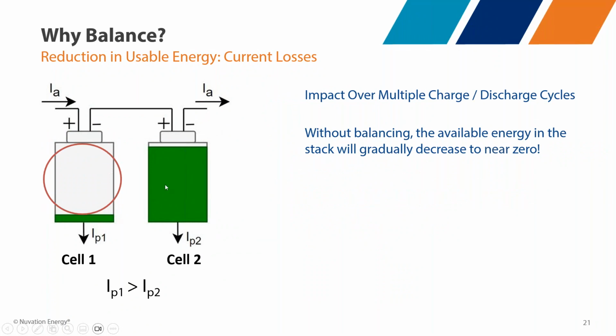If you go through a whole bunch of cycles without balancing over time, you'll end up with a very large difference in state of charge between these two cells due to the higher parasitic current in cell 1. We've actually seen systems like this in the field where balancing was not properly tuned, and you can get a real impact on the usable capacity of the system.